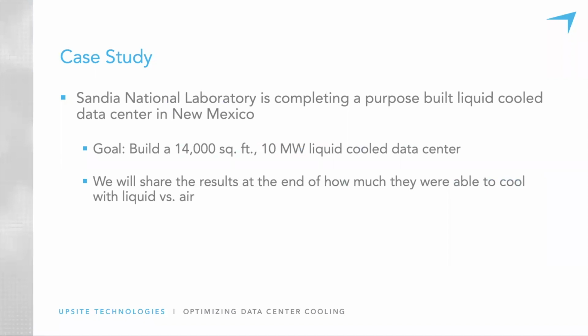All right, I want to plant a seed here and get you thinking a little bit. We have some information about a purpose-built liquid-cooled data center. Sandia National Laboratory is in the final stages of completing construction of a new data center built specifically to house liquid-cooled equipment. It's a 14,000 square foot facility, not very large, but dissipating 10 megawatts of power at full load. And they set out to have this facility be as focused on liquid cooling as possible.